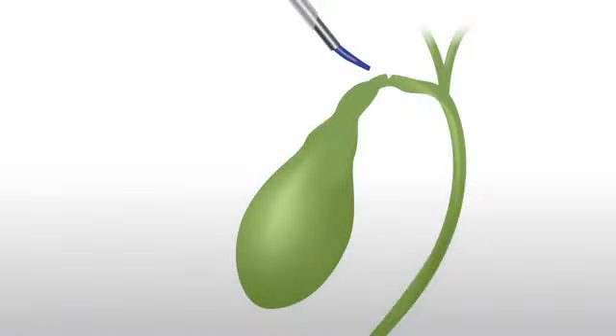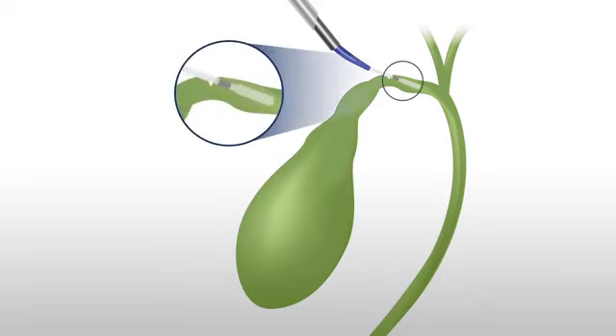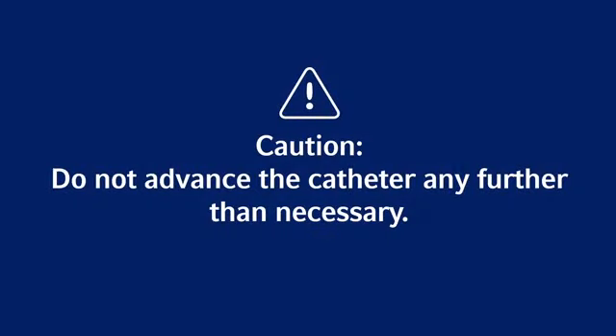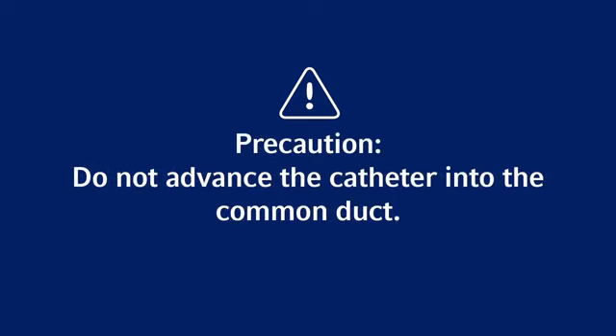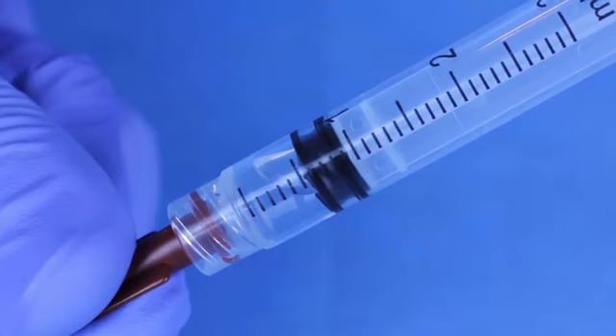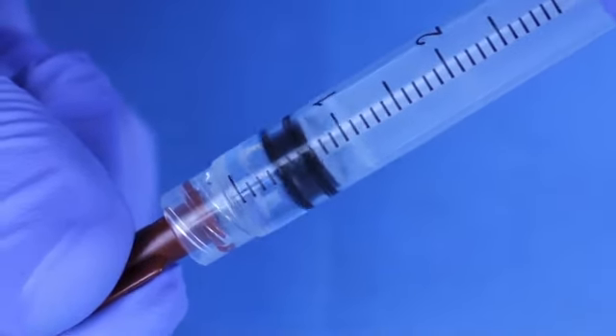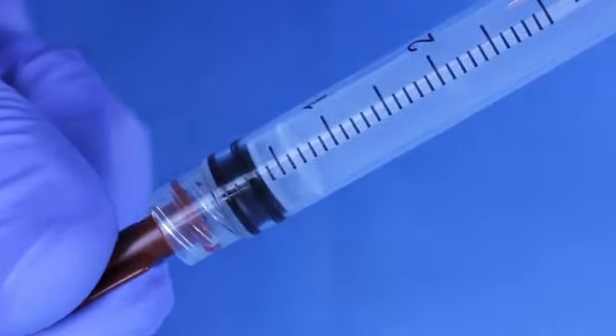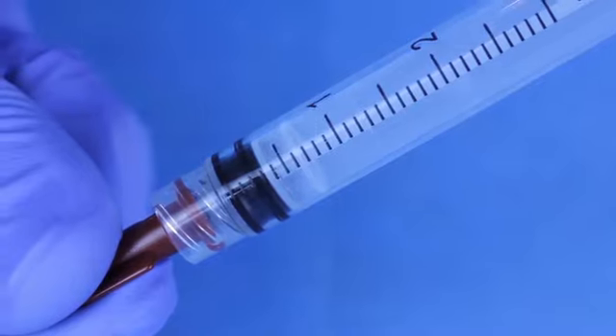Insert the balloon catheter through the guide catheter into cystic duct. Advance balloon catheter until black band proximal to balloon disappears. To aid with placement, additional black bands are located at 1 cm intervals referenced from the proximal end of the balloon. Caution: do not advance the catheter any further than necessary. Precaution: do not advance the catheter into the common duct. Inject saline through infusion port to verify that tip is not blocked by a valve in the cystic duct. If saline is difficult to inject, reposition catheter.